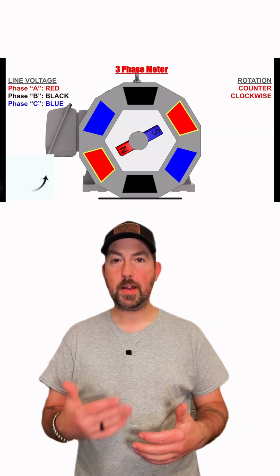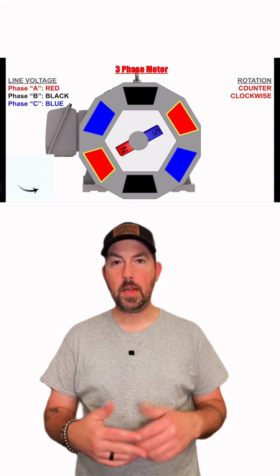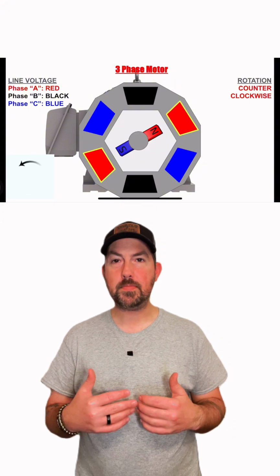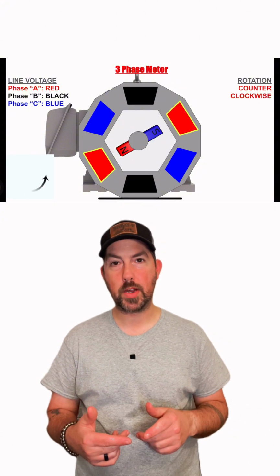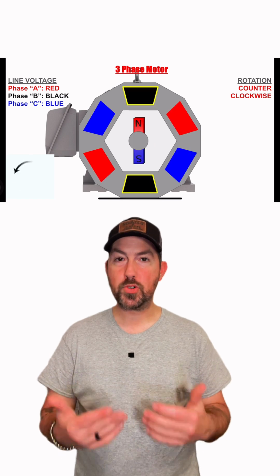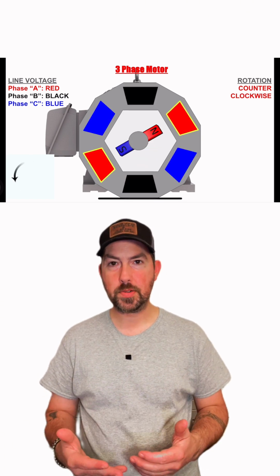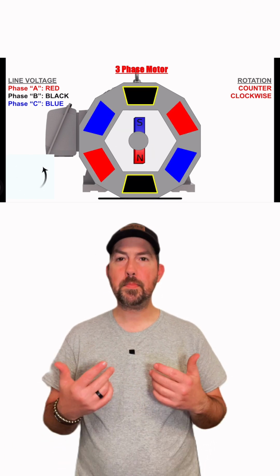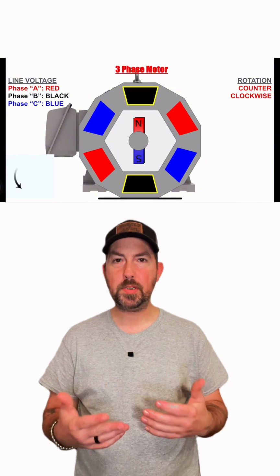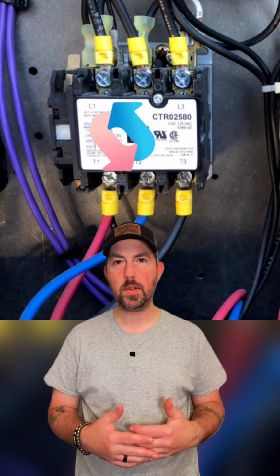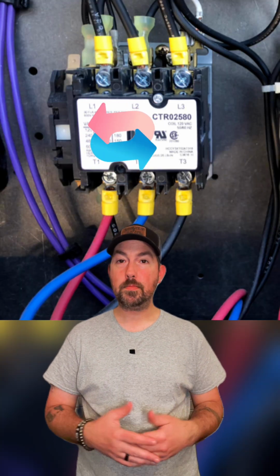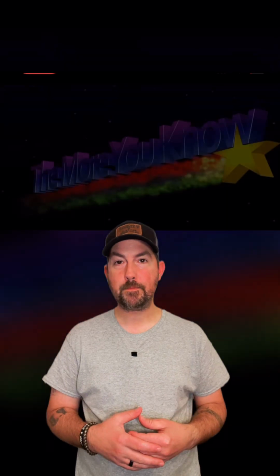If you switch two of the motor's power wires, you change the order of the phases from blue, black, red to red, black, blue. This changes the phase order and makes the magnetic field rotate in the opposite direction. And guess what? The motor's rotational direction is also reversed. So if your motor is spinning backwards, simply switch any two of the three-phase power wires and it'll spin the other way. Now you know why.